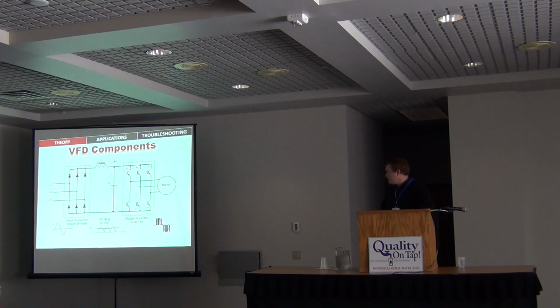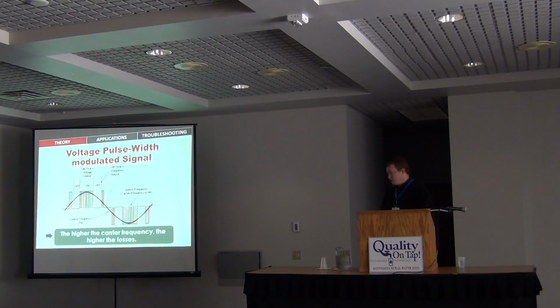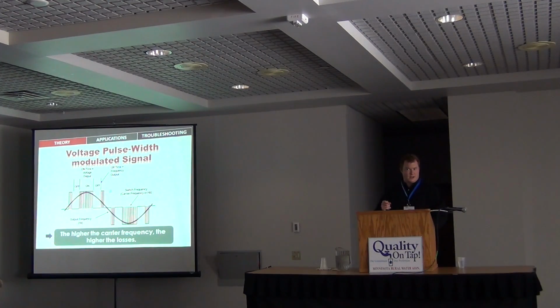And what you guys might run into is a motor that whines or makes noise, and you feel like you or some supplier or someone has to come out and adjust the carrier frequency of the VFD. And that carrier frequency is actually this really fast switching that's happening on the output side. So the higher the carrier frequency, which typically is between 8 and 16 kilohertz, the more losses you have. So if you have a VFD with a high carrier frequency, you might not hear it, but it's probably going to be putting off more heat, and your VFD may not last as long. So ideally, if you can keep that lower without creating a whine or a hum on your system, that's a good thing.